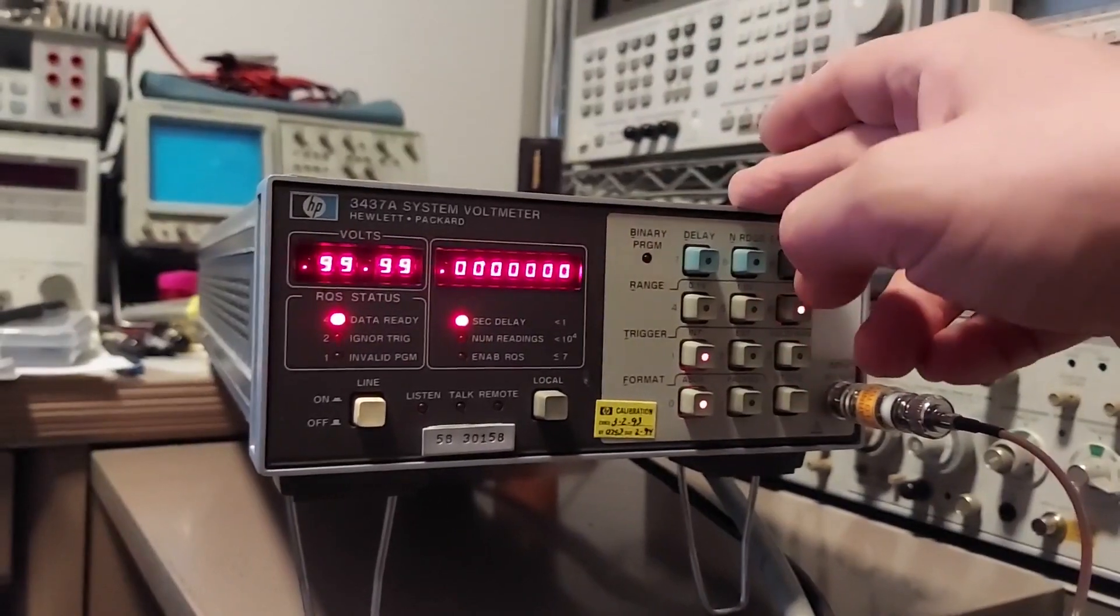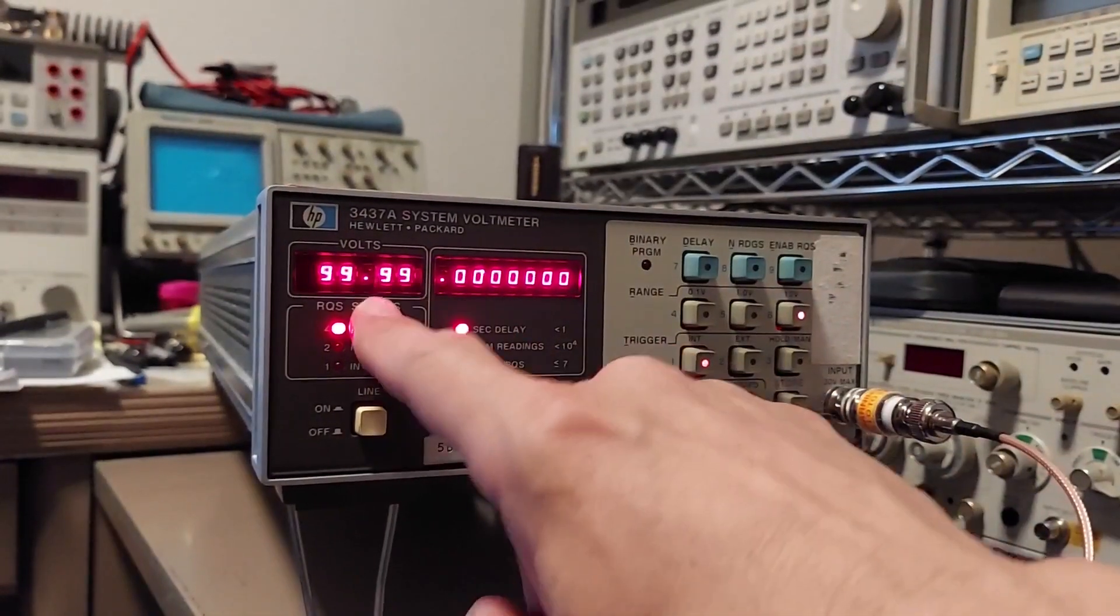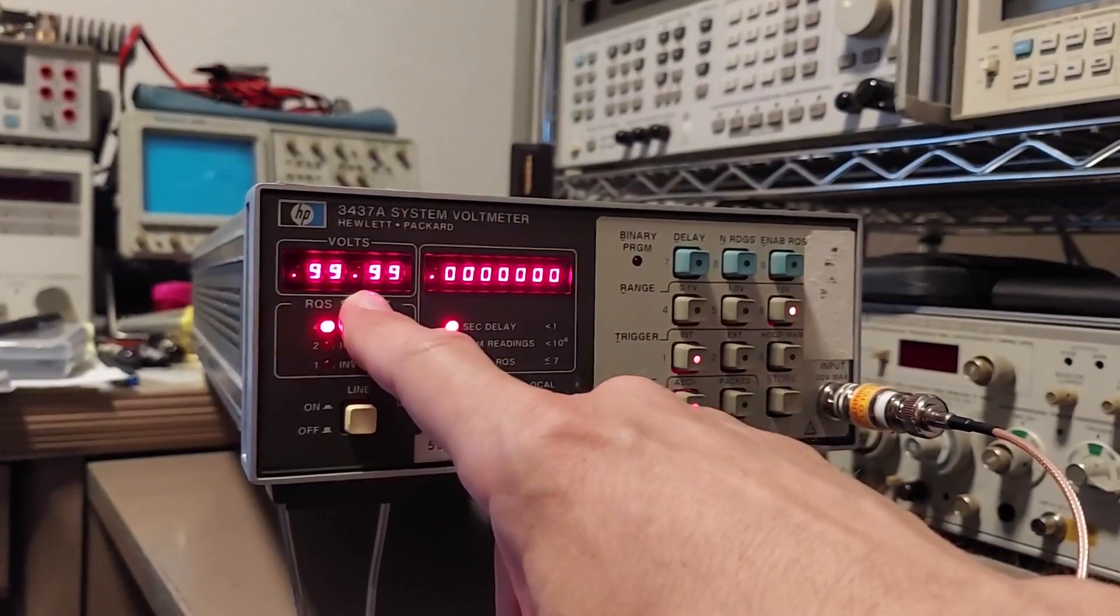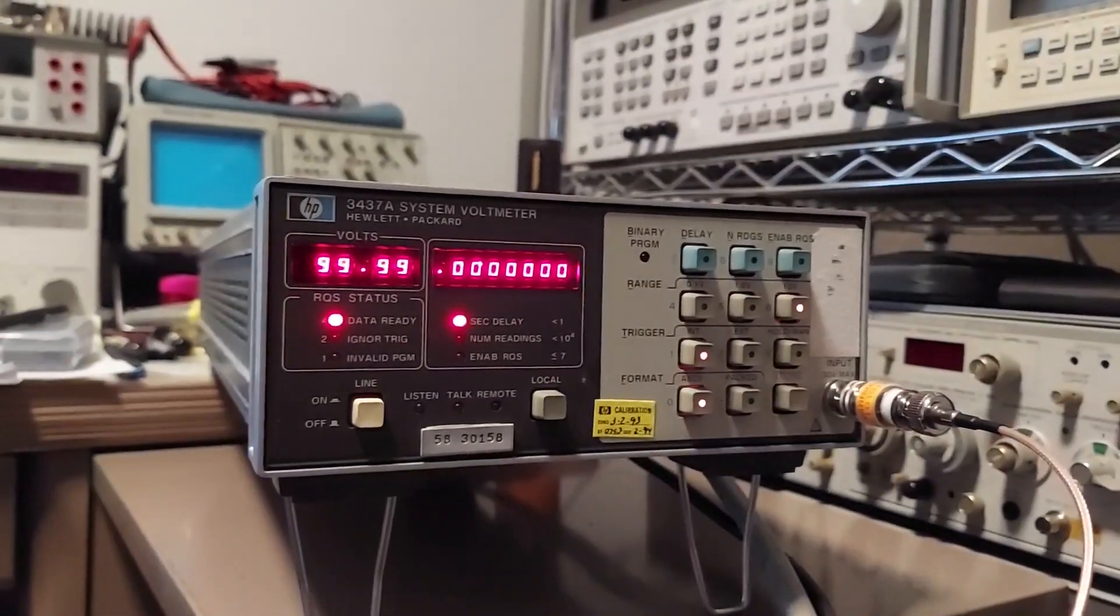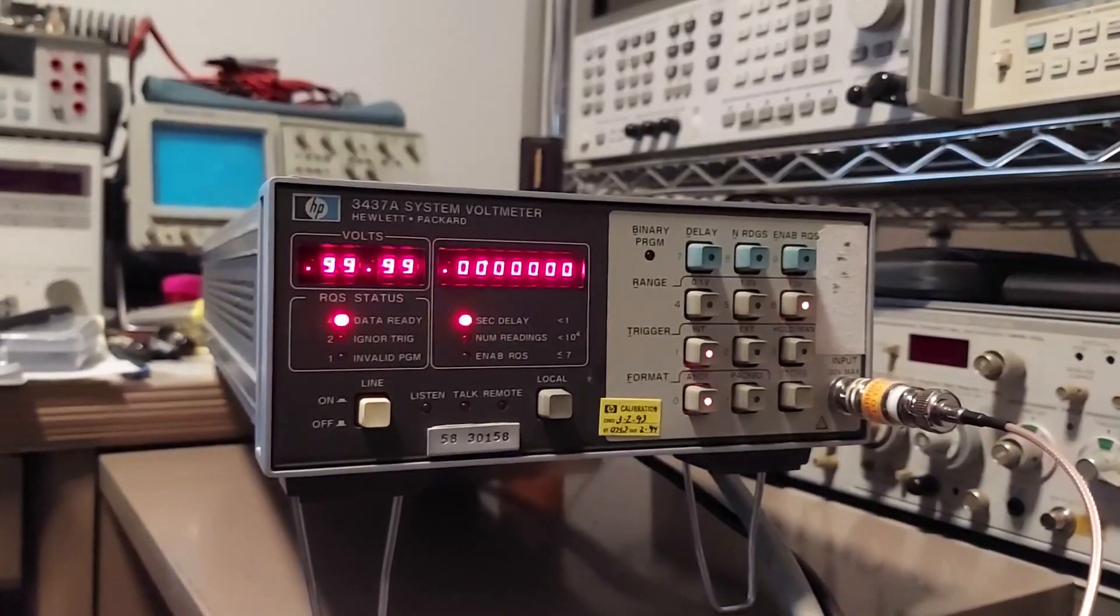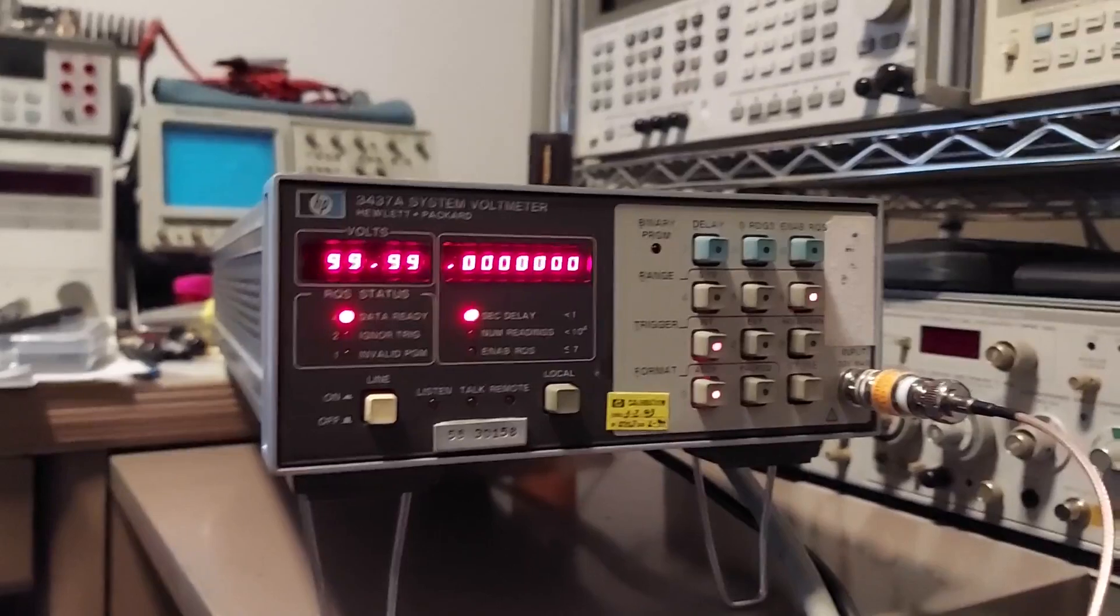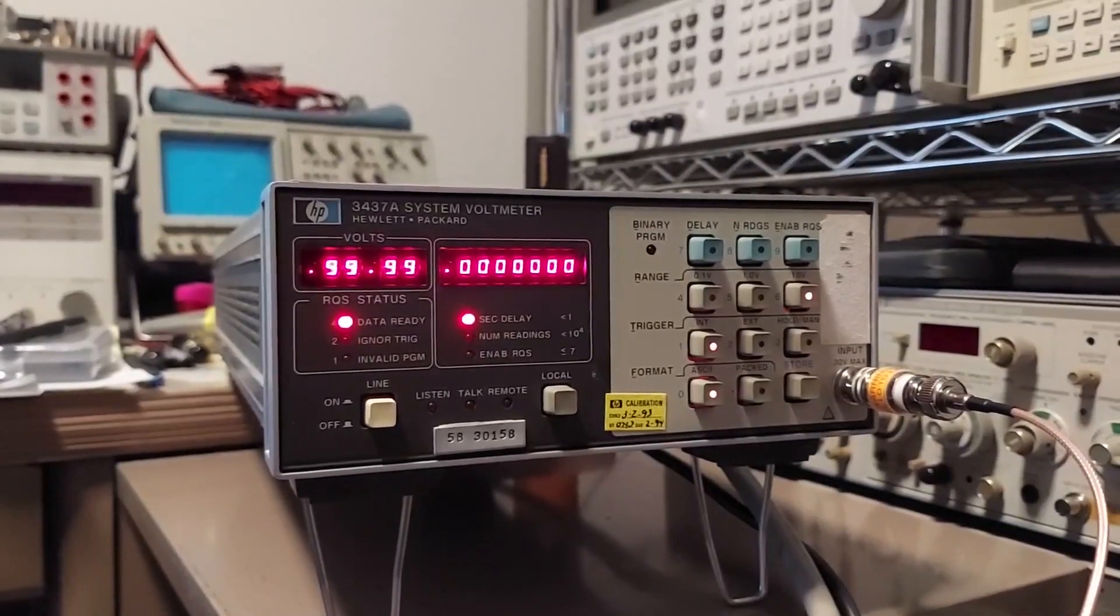There's some diagnostic LEDs inside, and there's two of them that are labeled zero and one. And the manual says that if any of those two LEDs are on, and you have the display showing all nines, the likely culprit is going to be U19, which is an opto isolator. So we're going to tear the thing apart and kind of dive into it. I got my opto isolators here the other day, so I bought 10 of them, so I have some extras on hand. And so we're going to open this thing up and see if we can fix it, get it working like it should.